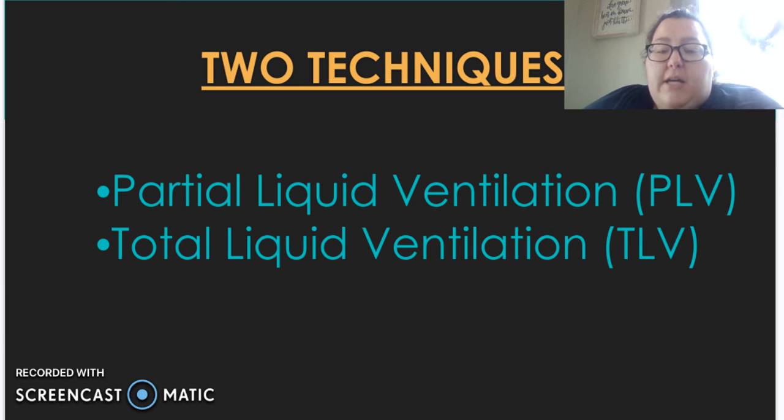They're filled with a volume equal to the FRC, approximately 30 milliliters per kilogram, and optimal CO2 clearance is at 4 to 5 breaths per minute. Early studies have shown it to be effective. It is accomplished with a system that is similar to ECMO.